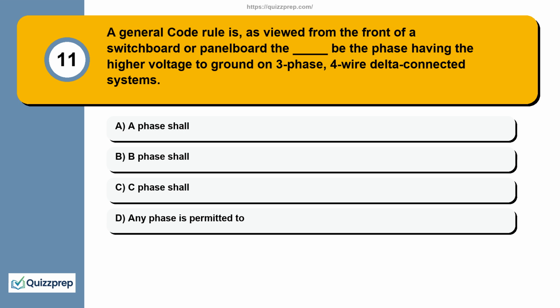Question 11. A general code rule is, as viewed from the front of a switchboard or panelboard, the __________ be the phase having the higher voltage to ground on 3-phase, 4-wire delta connected systems. A phase shall, B phase shall, C phase shall, any phase is permitted to.